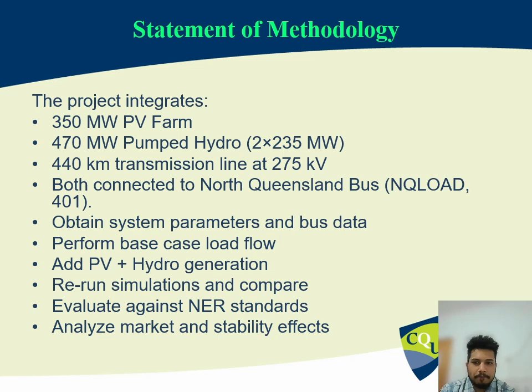Statement of methodology. There are a lot of project ingredients: we have to obtain a 350 megawatt PV farm, a 470 megawatt pumped hydro, and a 440 kilometer transmission line at 275 kilovolt. Both are connected to the North Queensland bus. We have to obtain the system parameters and bus data and perform the base case load flow, then add the PV plus hydro generation, rerun the simulation, compare against the NER standards, and analyze the market and stability effects also.